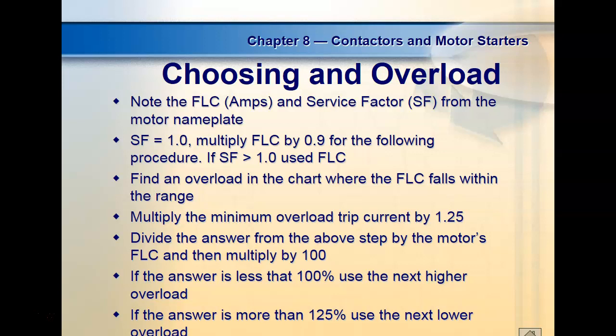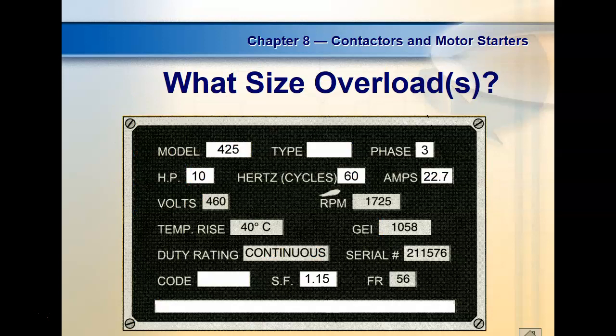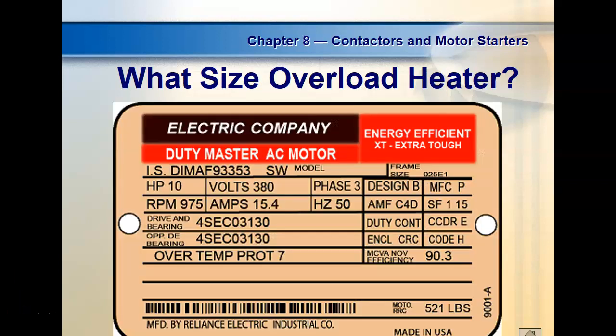Do it on your phone. You already know this. Okay. So what overload would I use for this? So this has got a service factor above 1, right? So that leaves off one step. What's the phase on it? 3 phase. So we use 3 units, right? Okay. 15.4 amps, full load current. What size would I start with?